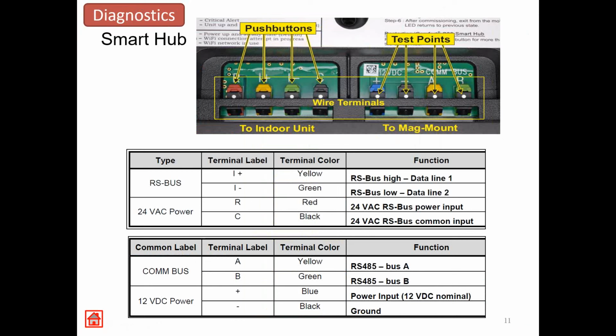Now, when we shift over to the right side, this is where we connect to the mag mount, that our display, or our thermostat, traditionally how technicians would refer to it, on the wall. We changed to 12 volts DC at that point. All 4 terminals are 12 volts. There's no 24 volts AC involved anymore. So that changes a little bit. And we want to make sure that you understand that that's what's going on.